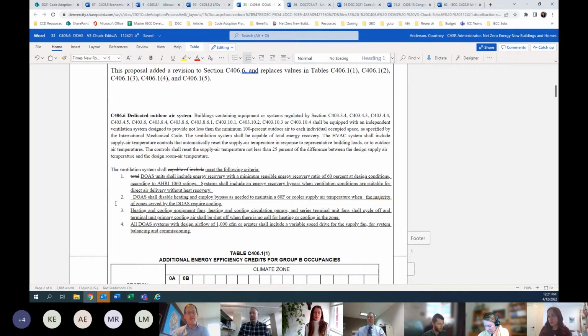Heating and cooling equipment, heating and cooling circulation pumps and series terminal units shall cycle off, and terminal unit primary cooling shall be shut off when there's no call for heating and cooling. And finally, DOAS systems with a design airflow of at least 1,000 CFM shall include a variable speed drive. And this is mainly used for these systems, even though they're primarily constant volume systems. Variable speed drives are commonly put on these systems for system balancing and commissioning. They want to be able to be tuned to provide the correct airflow once they're installed in the field.